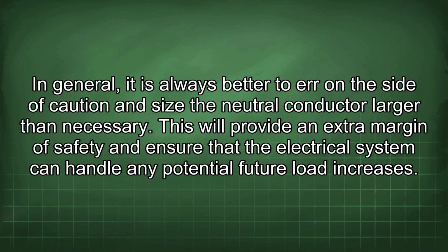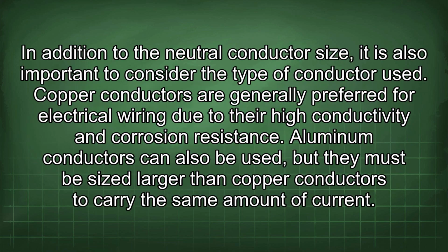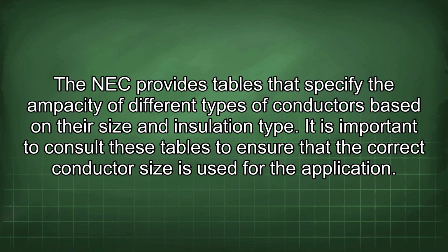In general, it is always better to err on the side of caution and size the neutral conductor larger than necessary. This will provide an extra margin of safety and ensure that the electrical system can handle any potential future load increases. In addition to the neutral conductor size, it is also important to consider the type of conductor used. Copper conductors are generally preferred for electrical wiring due to their high conductivity and corrosion resistance. Aluminum conductors can also be used, but they must be sized larger than copper conductors to carry the same amount of current. The NEC provides tables that specify the ampacity of different types of conductors based on their size and insulation type.